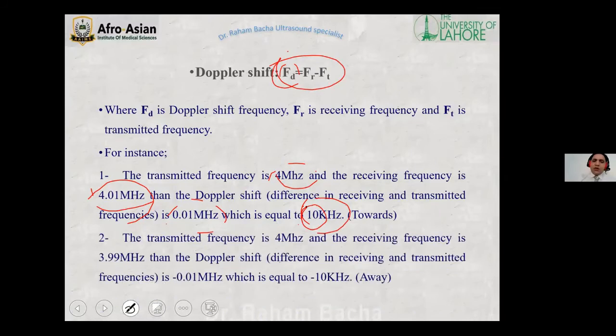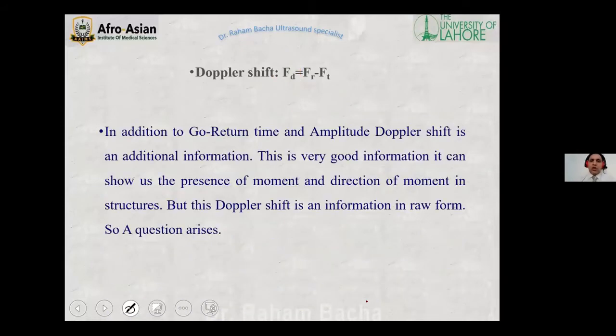In the second instance, the transducer operating frequency is 4 megahertz, and the receiving frequency is 3.99 megahertz. When we calculate the Doppler shift, it will be minus 0.01 megahertz, which is equal to minus 10 kilohertz. This minus sign shows that the reflector is moving away from the transducer. So if the Doppler shift is positive, the reflector is moving towards the transducer and the receiving frequency is greater than the transmitted frequency. If the reflector is moving away from the transducer, the receiving frequency will be lesser than the transmitted frequency, and the Doppler shift will be negative. You can calculate this with this formula.